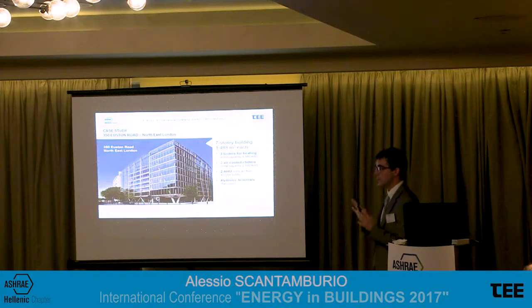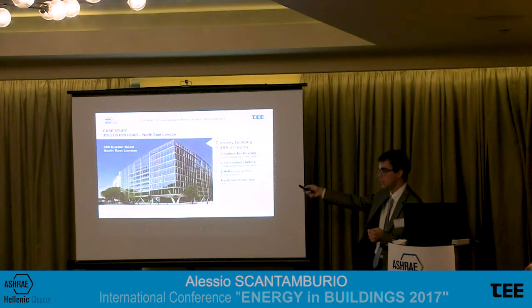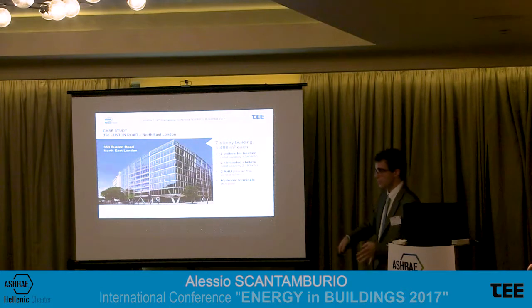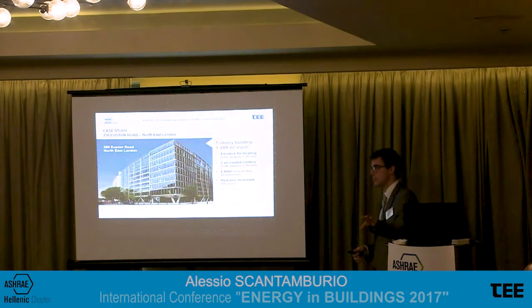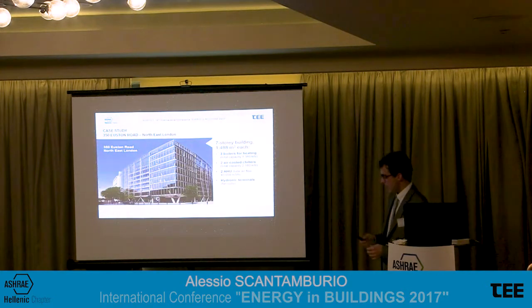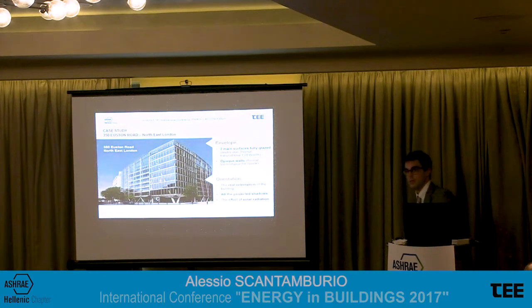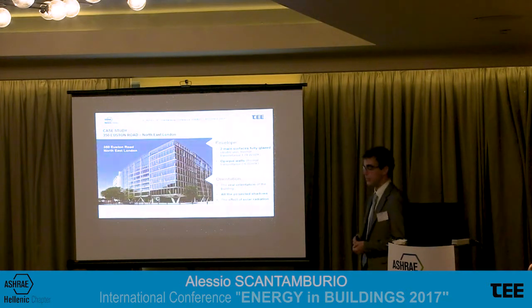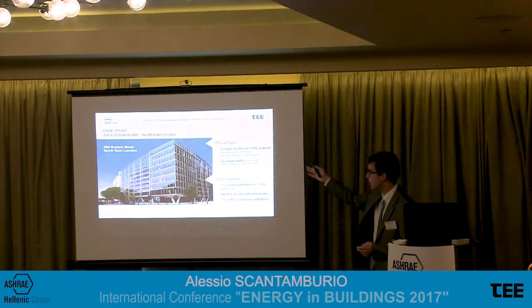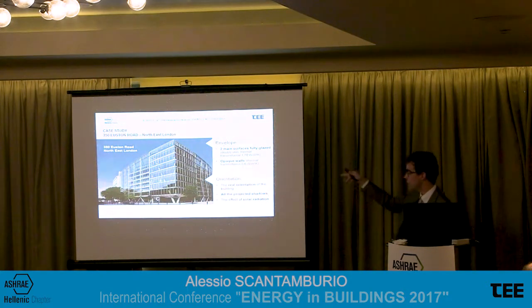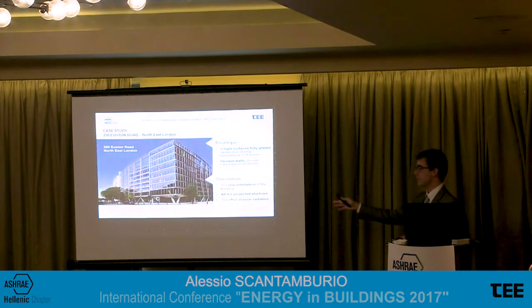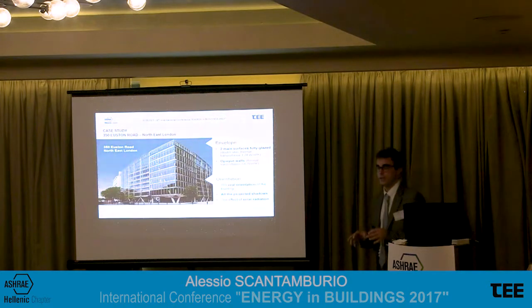Okay. This was and still is a 4-pipe building. This means that originally they had 3 gas boilers for heating, 2 air-cooled chillers for cooling. So a traditional system, a separate system for cooling and a separate system for heating. And we carried out an energy analysis, a dynamic energy analysis with TRNSYS software, taking into consideration, of course, the envelope of the building. So this means all the glazed surfaces or the opaque walls inside.